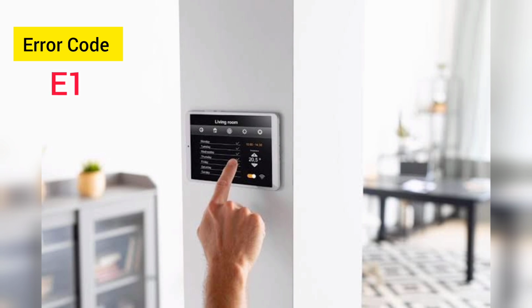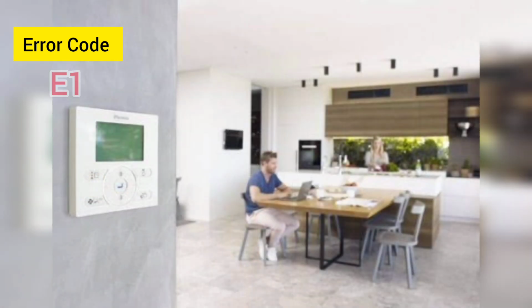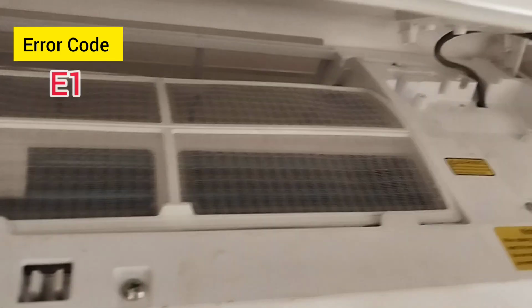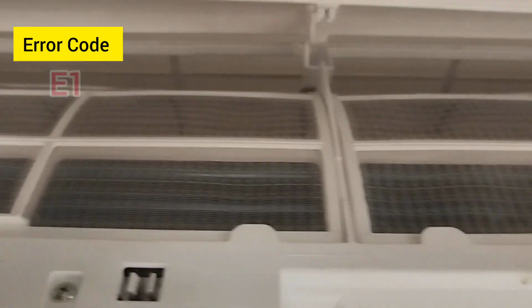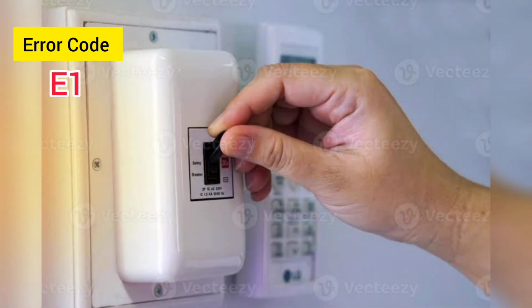Interference. Other electrical devices or wiring nearby could interfere with the communication signals. Dirty filters or coils. Restricted airflow due to dirty filters or coils can cause the unit to work harder and potentially trigger the E1 error.